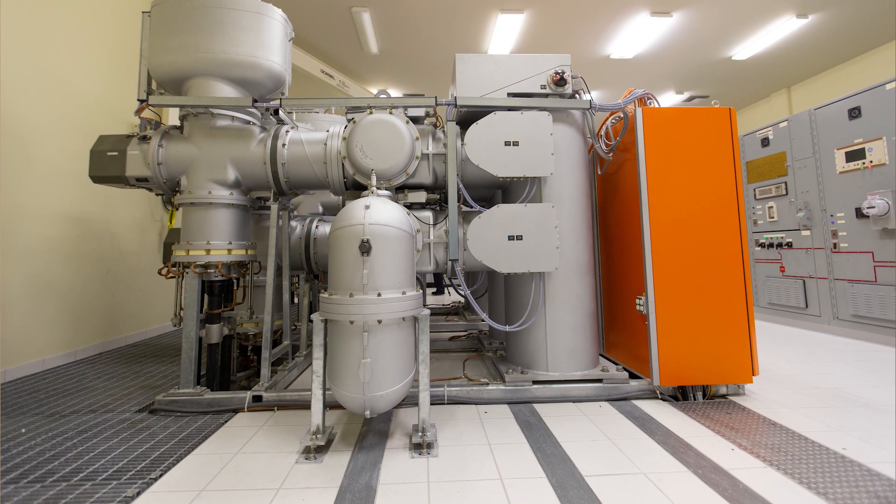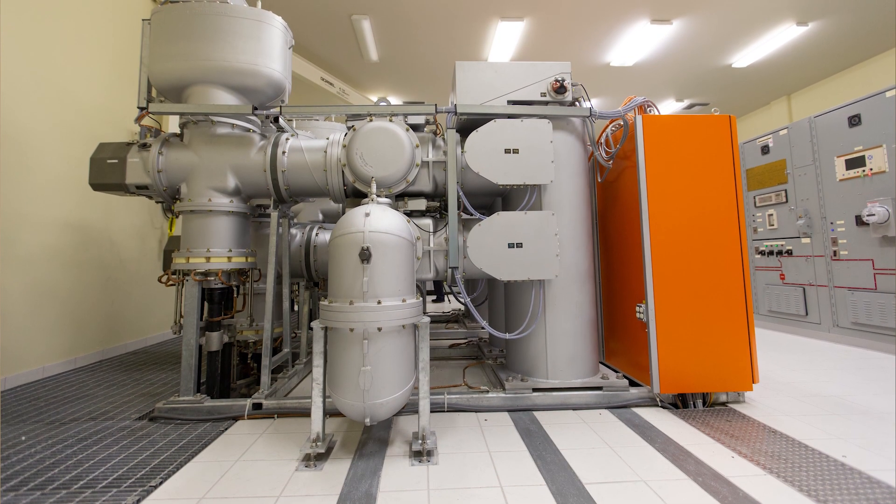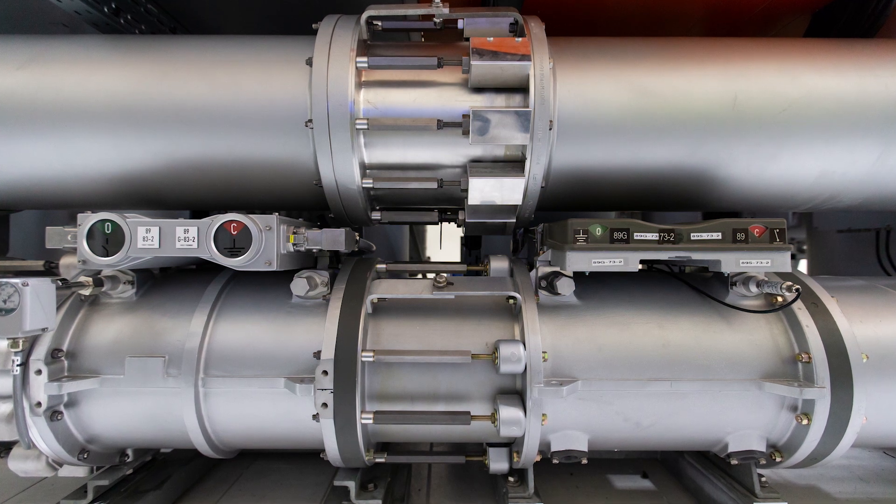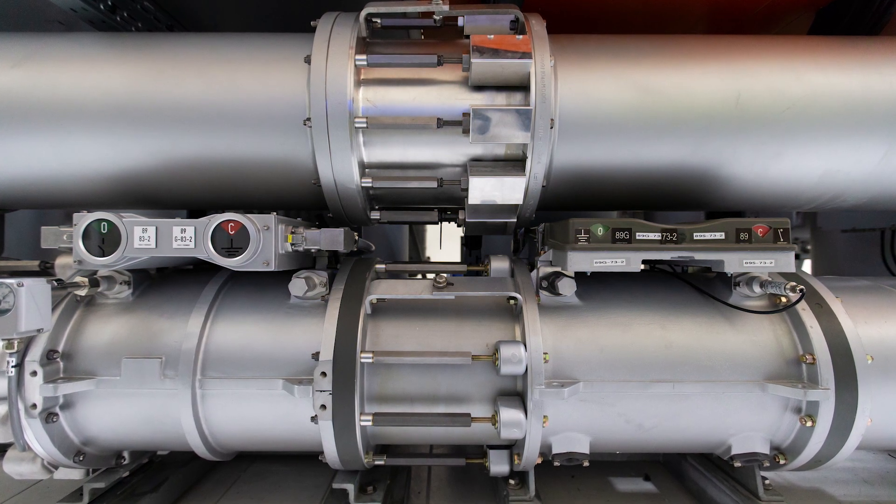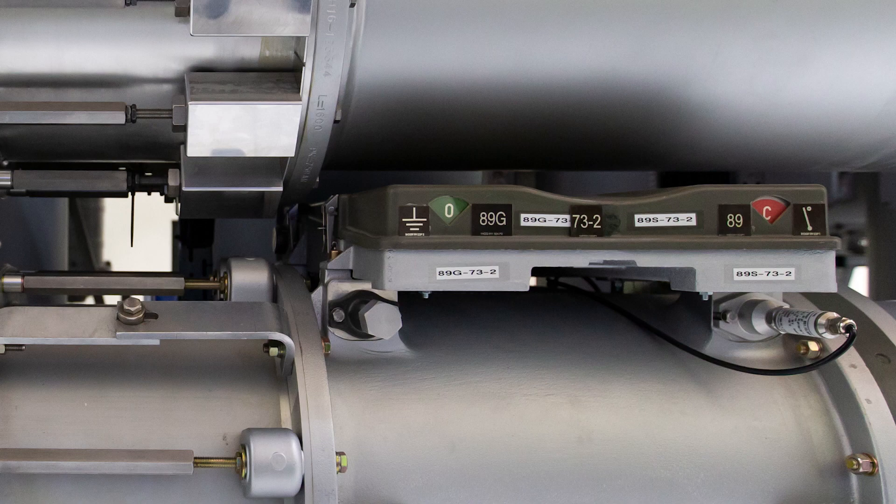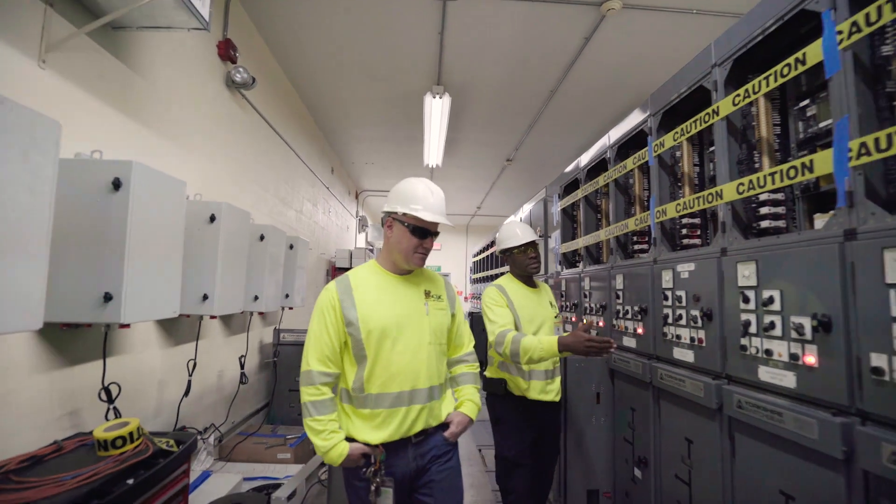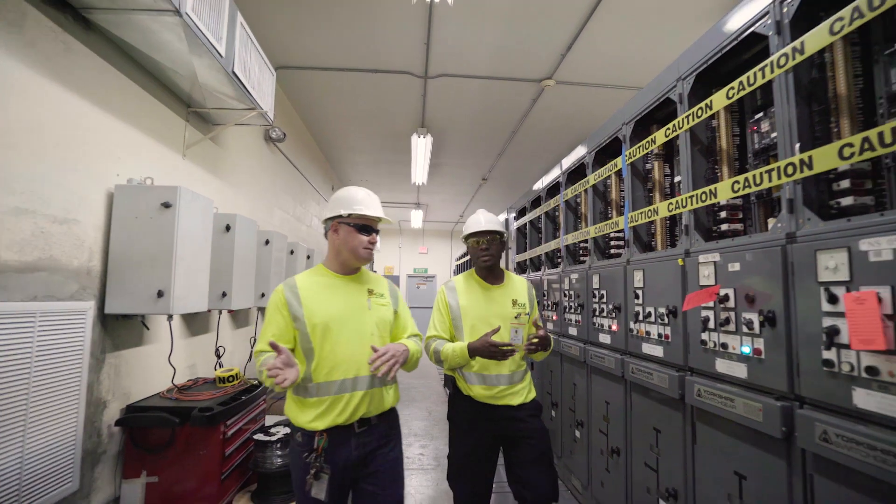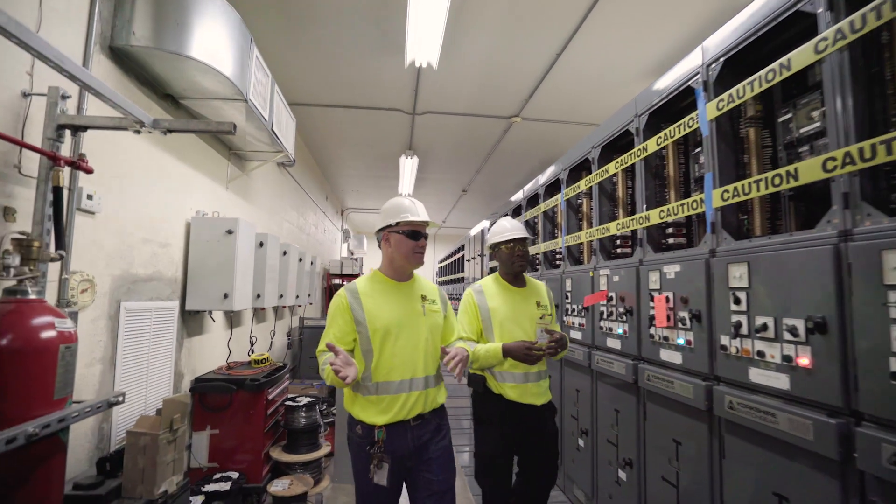The options we were presented with were pretty much GIS hardware changes to convert it to the latest type of switchgear. The manufacturer indicated that they need to replace the drive modules that control the switches and that was large cost as well as the bay controller itself. And that was the only option really. The other manufacturers that make switchgear needed that done first.